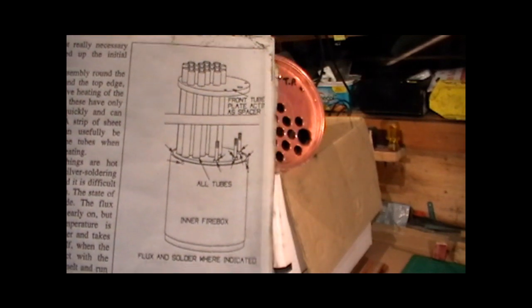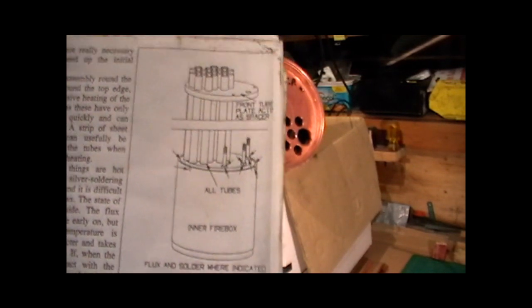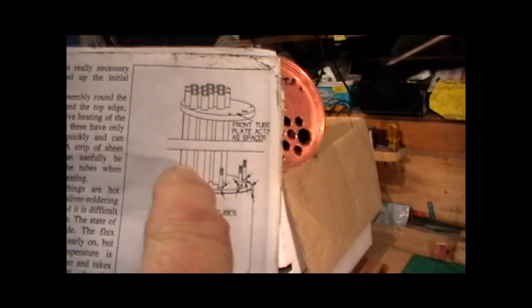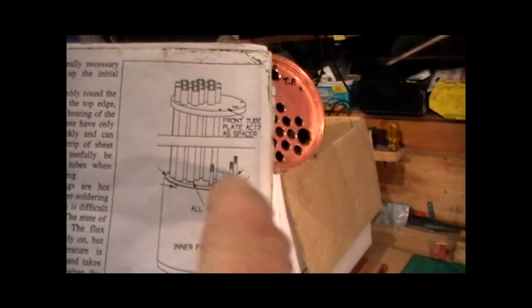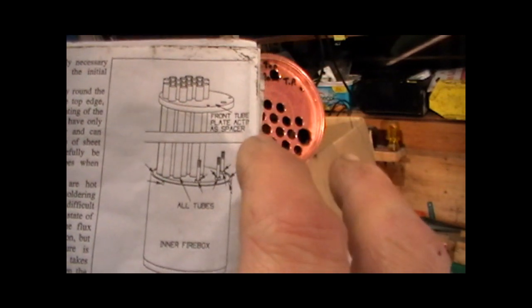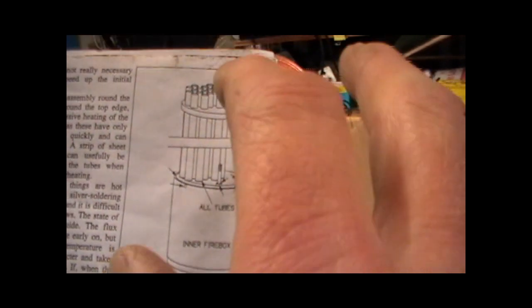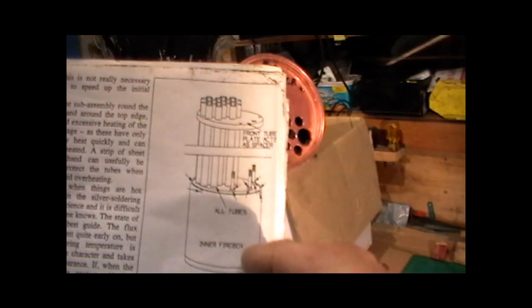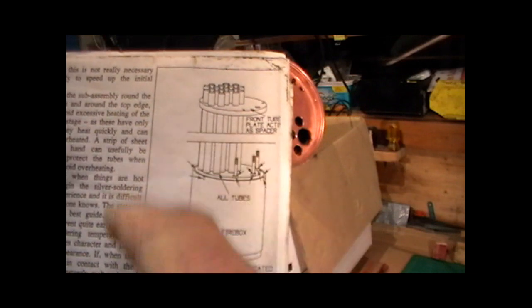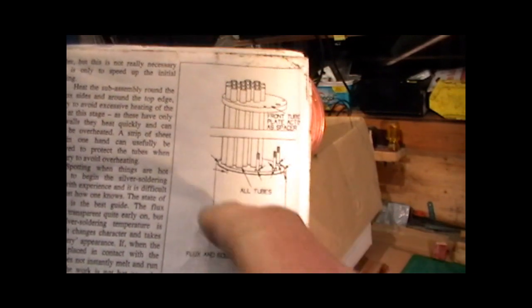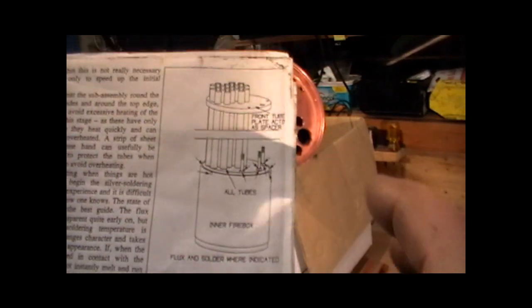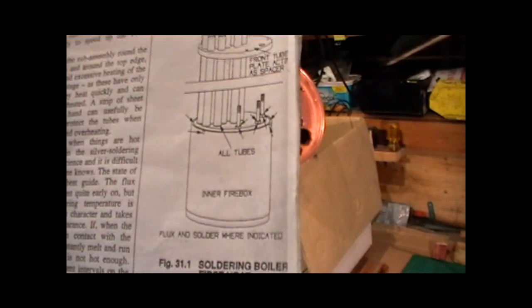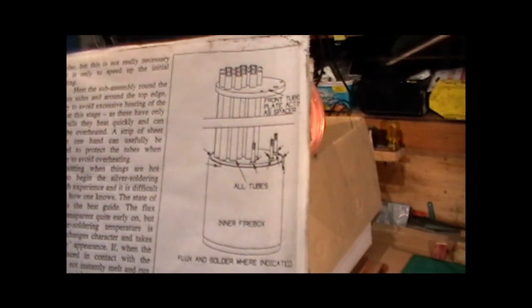My next stage will be to solder it up to that configuration. Then it'll have to be re-inspected by the inspectors so they can determine that I've got full penetration on all my internal solder joints before the outer tubes go on. So I'm given the go-ahead to go to that silver soldering stage, then re-inspect, and then once that's passed, I will be able then to put all the outer tubes on and all the fittings and finish the boiler off.